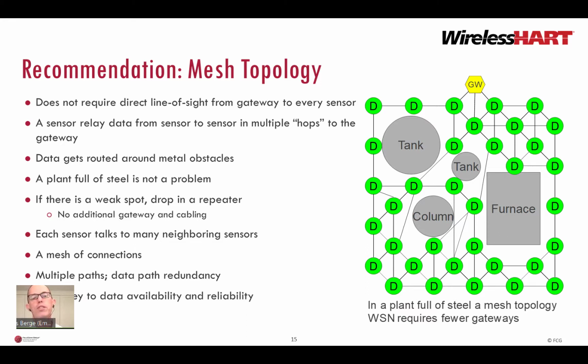WirelessHART solves this using mesh topology. A sensor which does not see the gateway directly instead communicates with a neighboring sensor which relays the communication to the next sensor and so on in up to 7 hops or more until it reaches the gateway. The data gets routed around metal obstacles. A plant full of steel is not a problem for the WirelessHART technology.